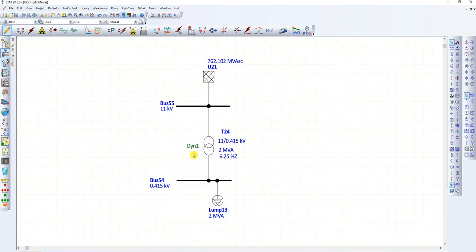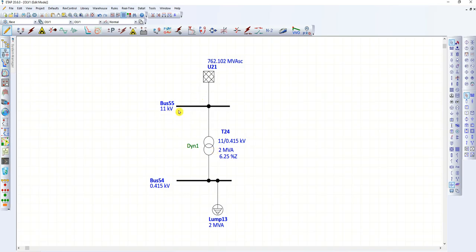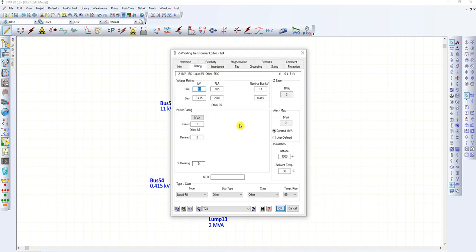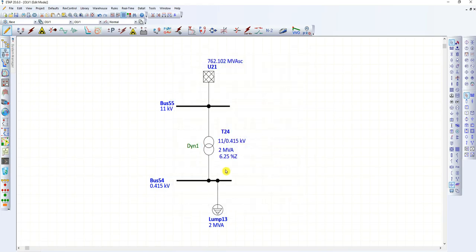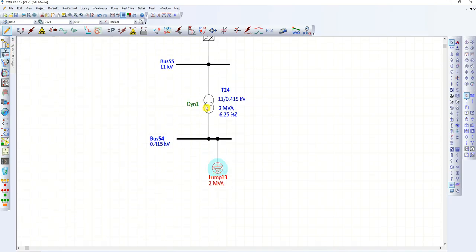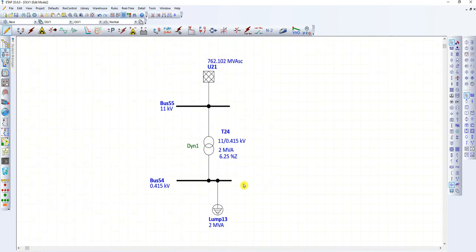Today's question is: can we connect a 2 MVA load in this network where the transformer rating is also 2 MVA? This system is 11 kV to 415 V, and the transformer rating is 2 MVA. A typical X/R ratio has been considered, and we are going to connect this 2 MVA load with this 2 MVA transformer. Should we connect it? As per IEC, what applies to this transformer?